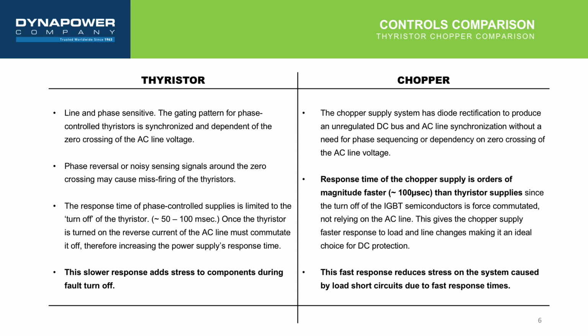Thyristor devices are phase sensitive with a gating pattern that has to be synchronized and dependent on zero crossing. The response time of phase controlled is dependent on turn-off time of the Thyristor and typically is between 50 and 100 milliseconds. Once turned on, the reverse current of the AC line must commute it off, increasing the response time and putting stress on components. Thyristor control is sensitive to the presence of noise on sensing and gate control signal wires, and misfiring of the devices can occur, causing damage to the system.